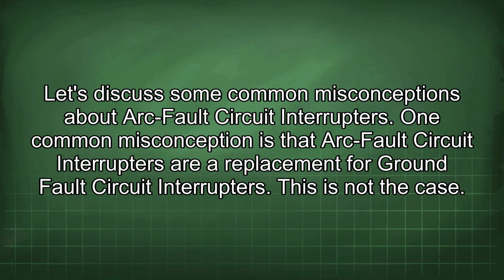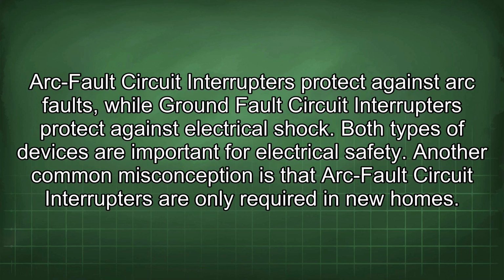Let's discuss some common misconceptions about arc fault circuit interrupters. One common misconception is that arc fault circuit interrupters are a replacement for ground fault circuit interrupters. This is not the case. Arc fault circuit interrupters protect against arc faults, while ground fault circuit interrupters protect against electrical shock. Both types of devices are important for electrical safety.